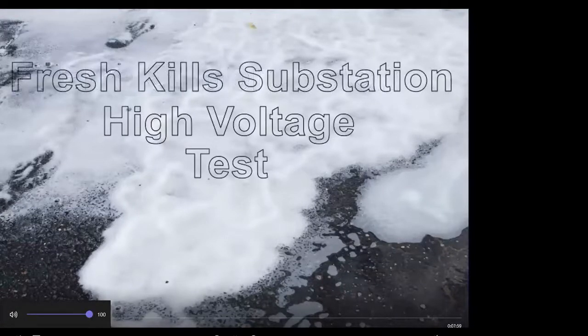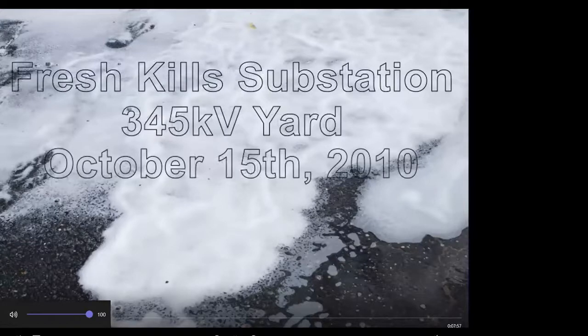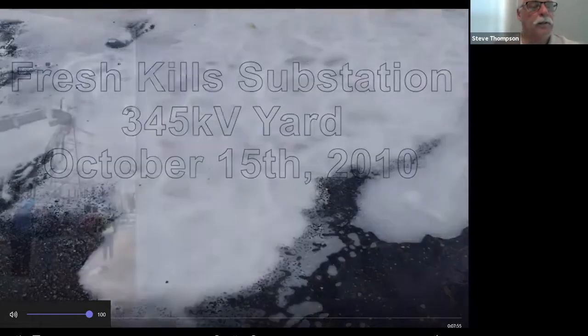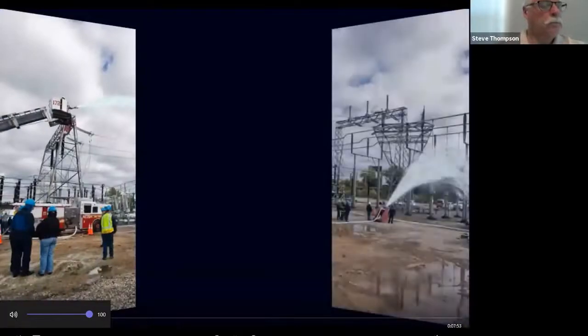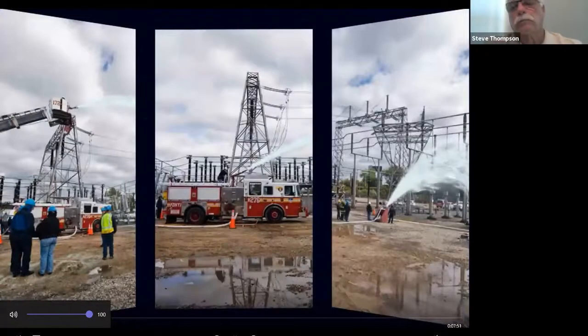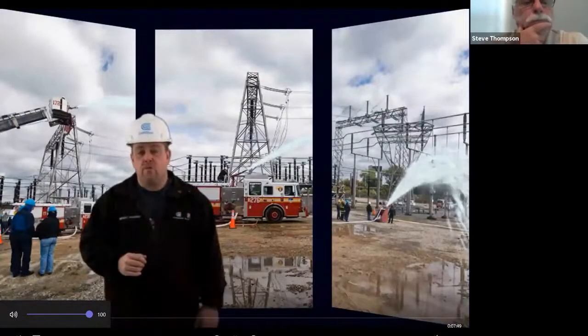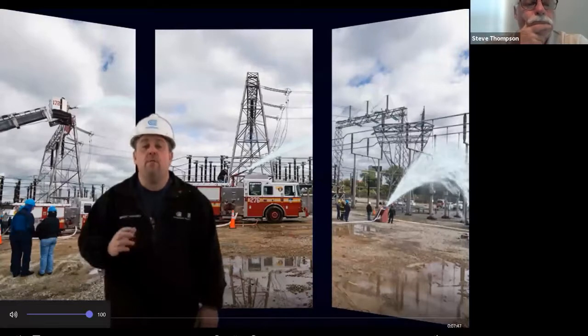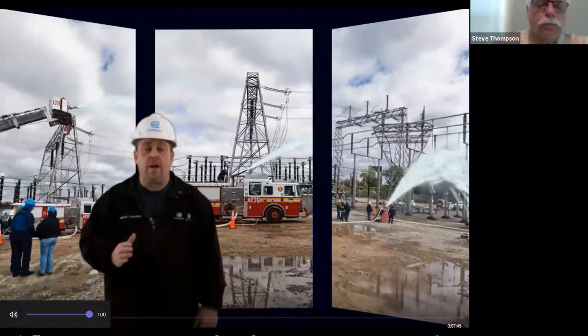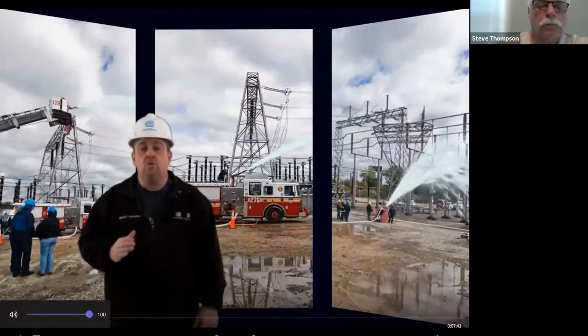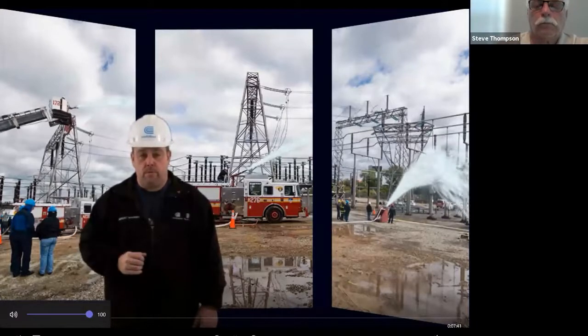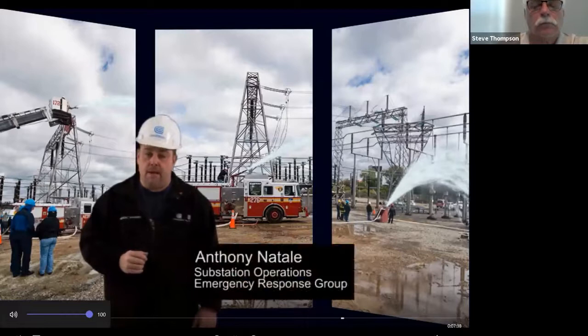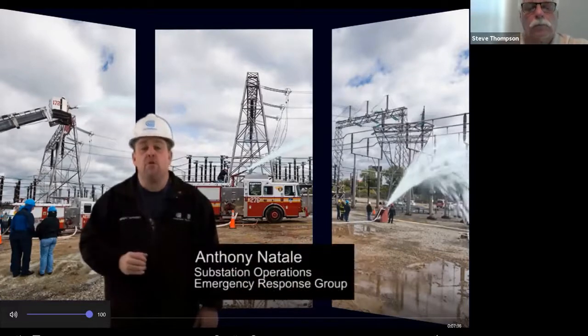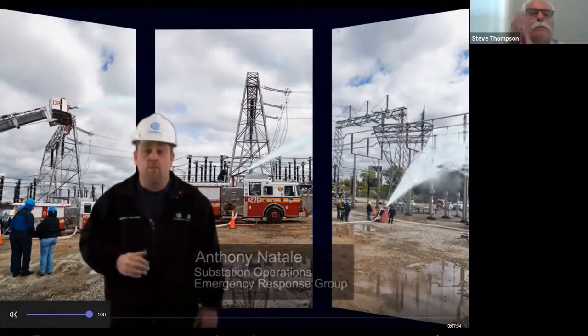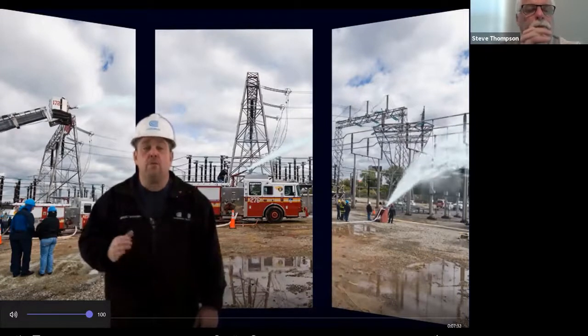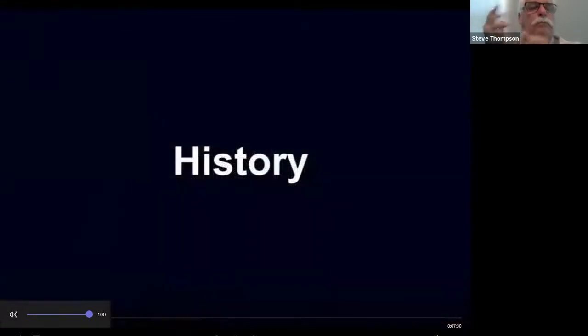Steve, can you hear that? On October 15, 2010, Con Edison and the FDNY conducted a live suppression test at the Fresh Kills 345,000 volt substation. The purpose of the test was to measure leakage current from the high voltage conductors back through the suppression agent to the fire department apparatus. Hello, my name is Anthony Natale, and I'm with Substation Operations Emergency Response Group. Before we get to the results, here's a brief history on the project.